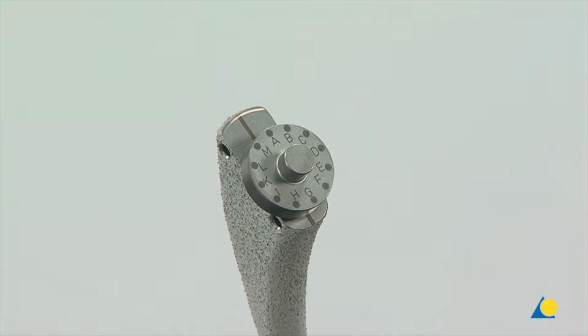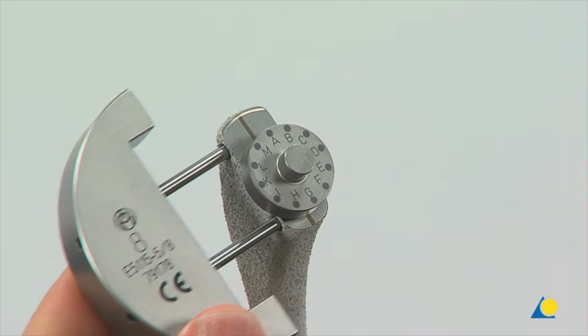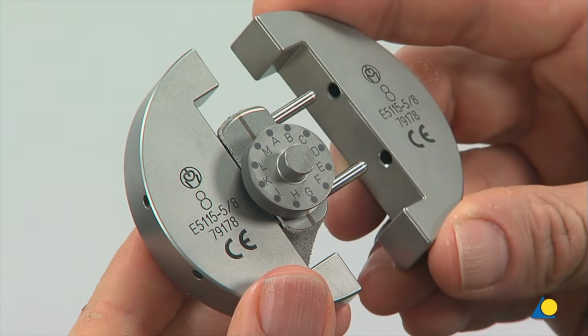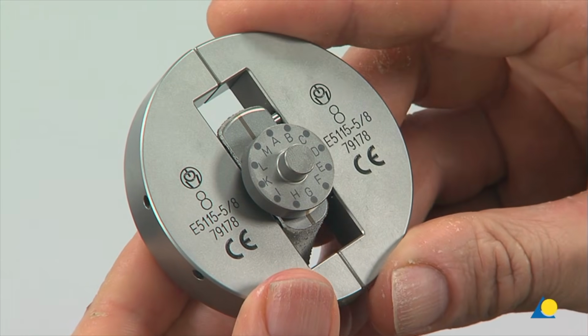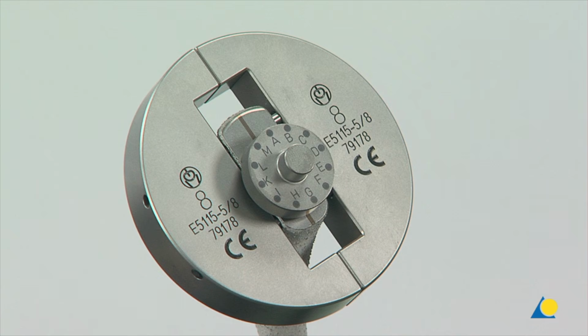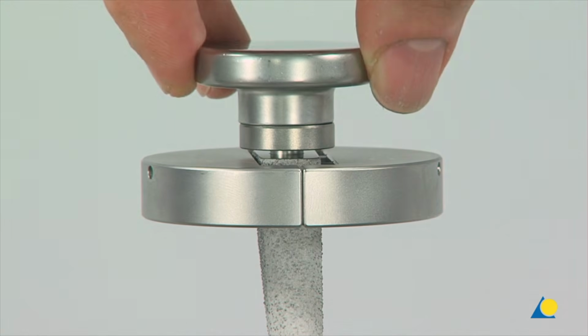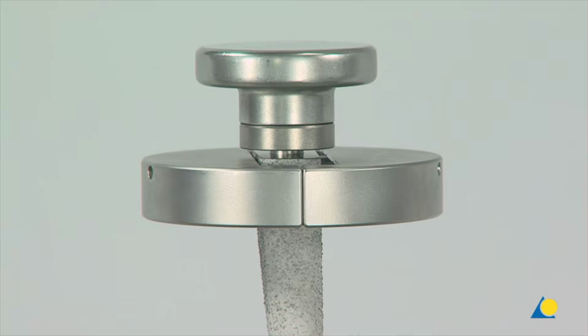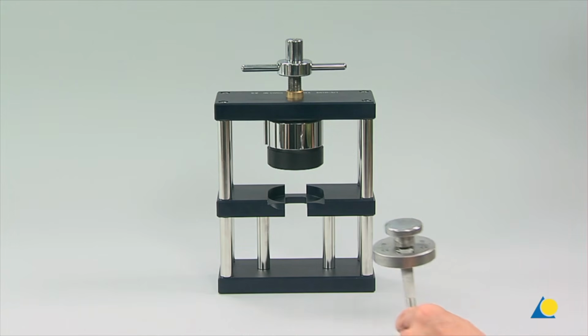The stem holder, corresponding to the size of the shaft, is chosen. This assembly allows the stem to be firmly held in the press. It is important that the etched side of the stem holder is facing up. Improper assembly may cause jamming. The eccenter impactor is mounted on the eccenter. The assembly is placed in the press.